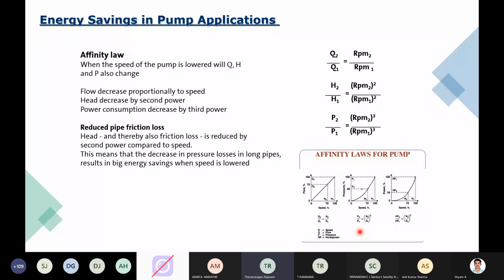The idea of all this is tied to the basic law, the affinity law, which is well known and widely used in pumping applications. It defines the impact on flow and head with variation in speed, that is flow variation, pressure variation, and also power variation. So the impact of a reduction is reflected three times on your energy consumption. That is the purpose. We always insist on going for a speed control approach wherever possible.